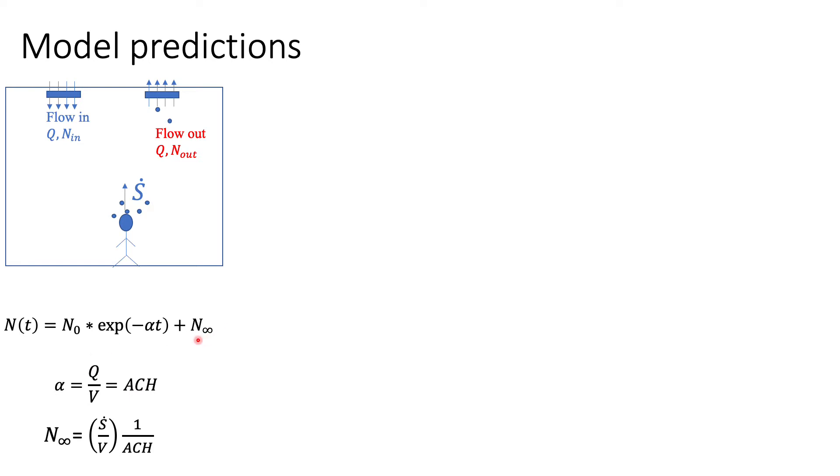The concentration at a large time, the first term will drop out, you will reach a steady state concentration N infinity. That steady state concentration depends on how much you're putting out per second, the volume of the room, and the air changes coming in.